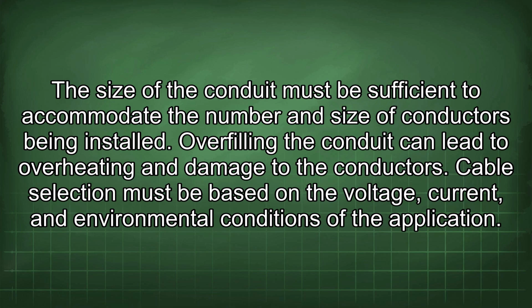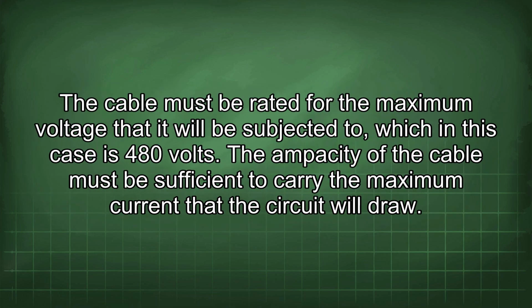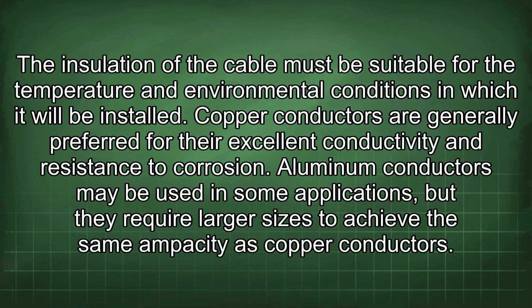Cable selection must be based on the voltage, current, and environmental conditions of the application. The cable must be rated for the maximum voltage that it will be subjected to, which in this case is 480 volts. The ampacity of the cable must be sufficient to carry the maximum current that the circuit will draw. The insulation of the cable must be suitable for the temperature and environmental conditions in which it will be installed. Copper conductors are generally preferred for their excellent conductivity and resistance to corrosion. Aluminum conductors may be used in some applications, but they require larger sizes to achieve the same ampacity as copper conductors.